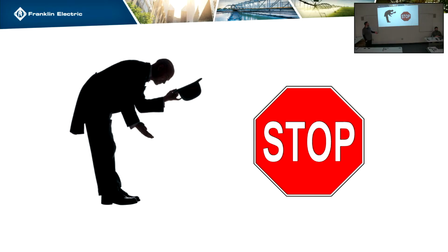So basic is going to have one set of defaults that's basically 0. It's not going to be set up for anything. Okay. And then when you get into things like the supply fans, it changes your starting point. So there's less things that you have to go through and set up. A prime example is a submersible pump: if you set that, it's not going to work with any fan. It's got a 2-second acceleration time. There's just a bunch of stuff that wouldn't work. So it goes through and changes all your acceleration times and your normal protection settings, so that you wouldn't have to change them. You can just keep going.